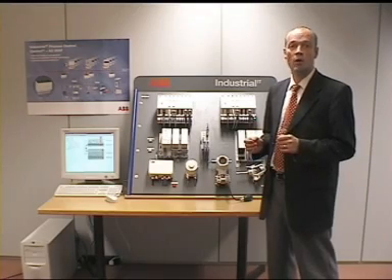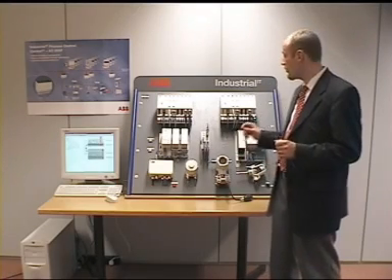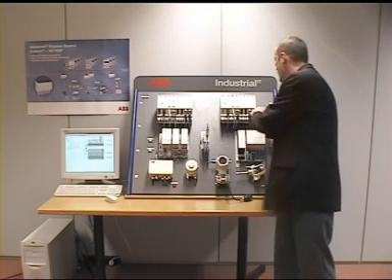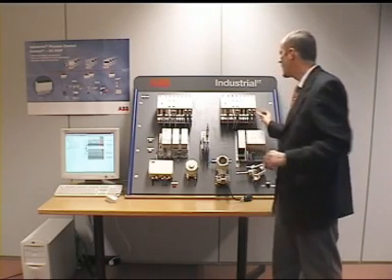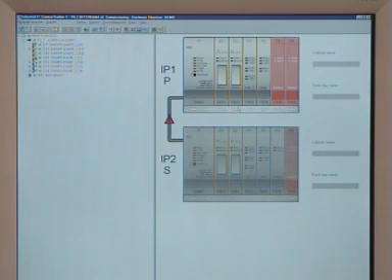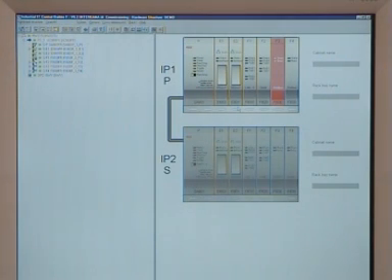When the problems are fixed I just reconnect the PROFIBUS line again to the controller and after a very short while it is detected as healthy again, that means this controller can take over the process again if there is a problem.